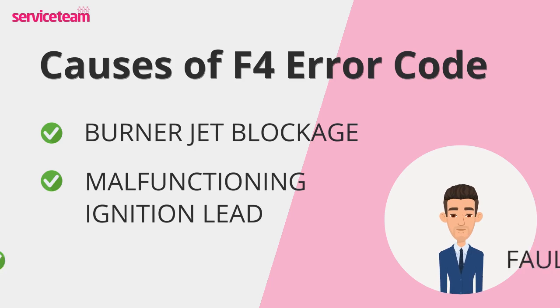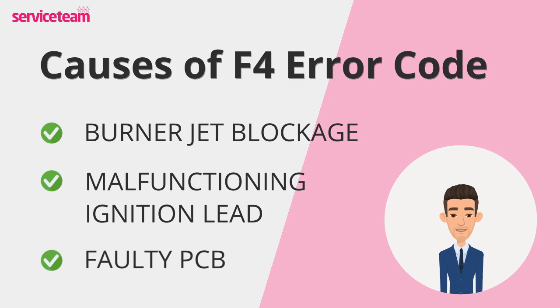A malfunctioning ignition lead, responsible for lighting the gas, can lead to an F4 error by preventing the boiler from igniting properly. If none of these problems are the culprit, the issue may lie with the PCB itself, which could trigger the F4 code even if all other components are working properly.